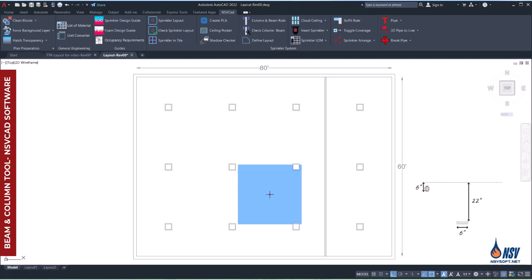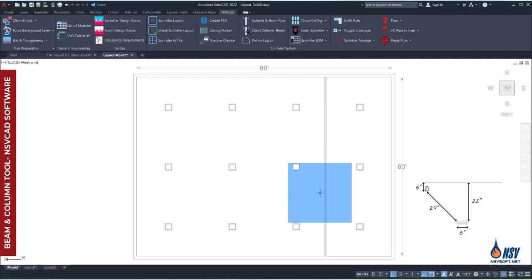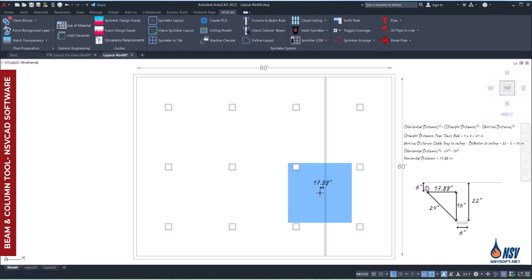For the cable tray, the minimum permitted straight line distance is 24 inches. In the plan view, we see that the horizontal distance comes out to 17.88 inches. This value is automatically calculated by the software based on the vertical distance between the deflector and the cable tray, using the Pythagorean formula.